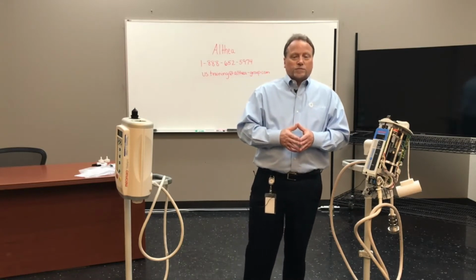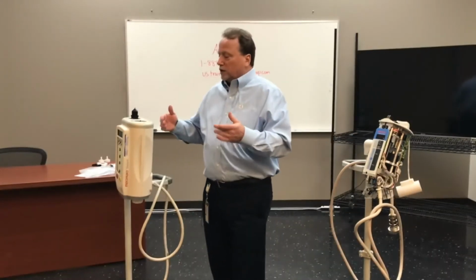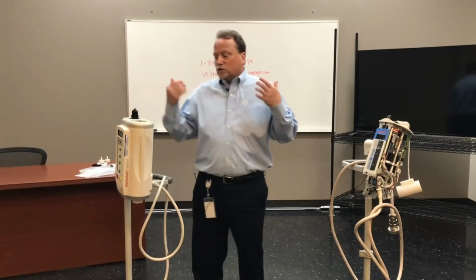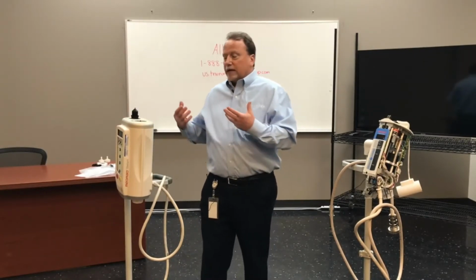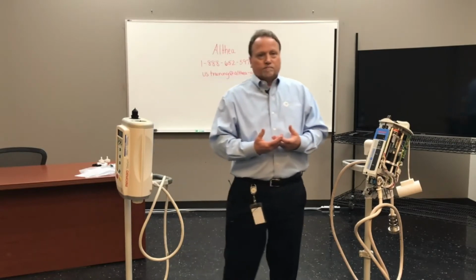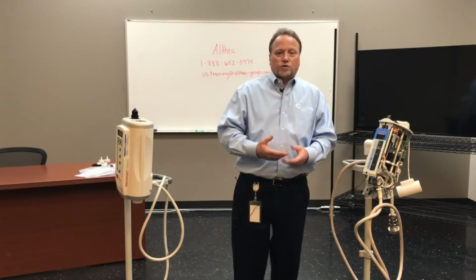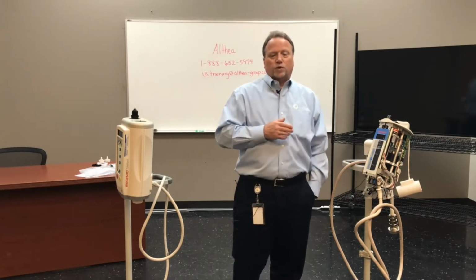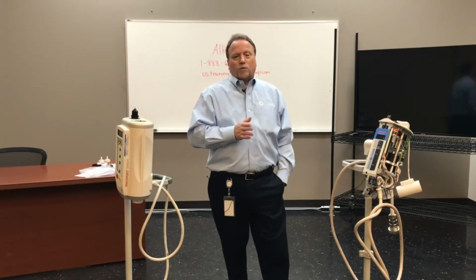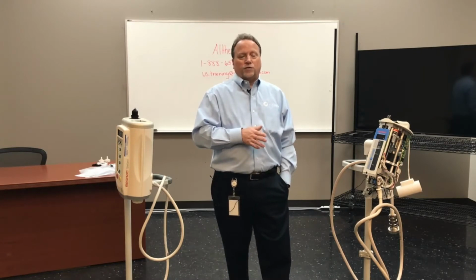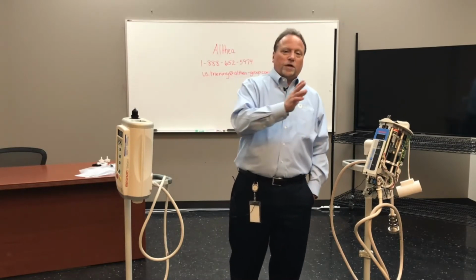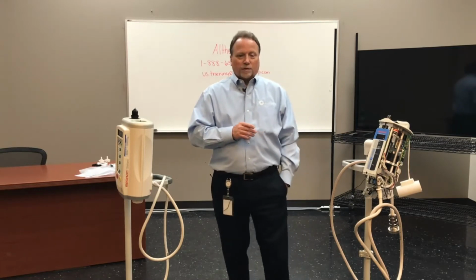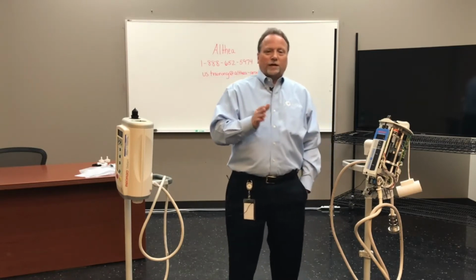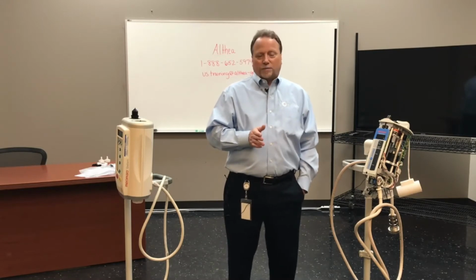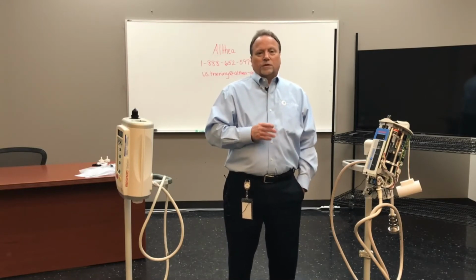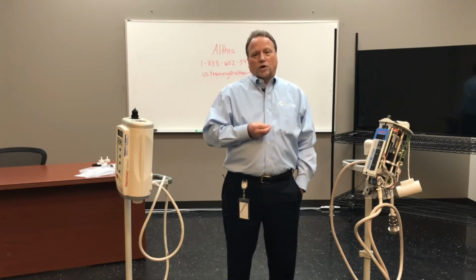So resolve the issues. Okay, so you've gone in, you've inspected the system. It's going to take you 2 hours to do the PM, and now it's time to do the PM. Record the protocol on the screen. Record that protocol. It's so important to put it back the way you found it. Don't leave a test protocol on the screen. They may inadvertently use it on a patient, and that's not good for anybody, particularly the patient. So always record the original protocol on the screen.